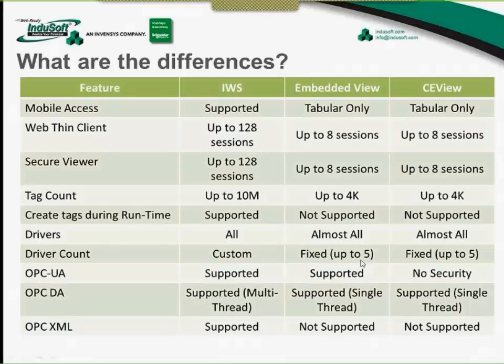So again, it's a limitation, but not because we want it to be a limitation. OPC DA: InduSoft Web Studio supports a multi-threaded OPC DA, and this multi-threaded OPC DA is not available on Embedded View and CE View. In other words, you do have OPC for data access across all the different products. What multi-threaded means is that if you're connecting to multiple servers at the same time, and you use the multi-threaded option, if one server goes down, the other ones will remain working fine.